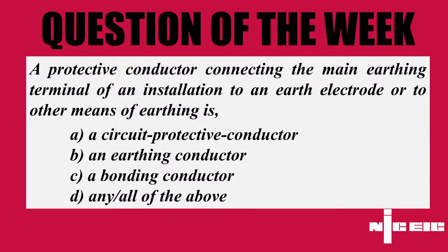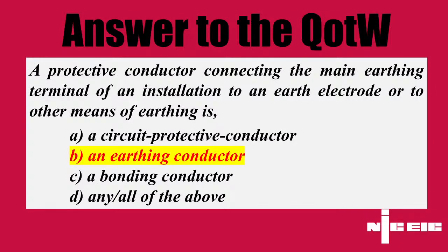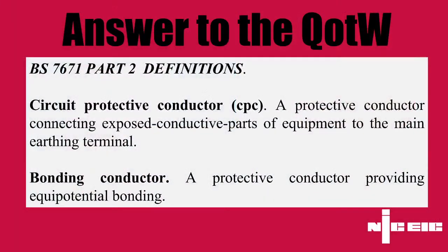Well, straight away we'll go in and say that the answer is B, an earthing conductor. And as you've already said, Sam, the key to questions like this relies on Part 2 of BS 7671, where we do have the definitions for anything that we're unsure about. Possible answer A, a circuit protective conductor, if we looked in Part 2, would be a protective conductor connecting exposed conductive parts of equipment to the main earthing terminal. So that didn't quite fit our question. Possible answer C, a bonding conductor. Again, by reference to Part 2 of the definitions, a protective conductor providing equipotential bonding. So again, didn't quite fit what we were looking for. And then the actual answer is B, the earthing conductor, which connects the main earthing terminal of an installation to an earth electrode or to the other means of earthing.